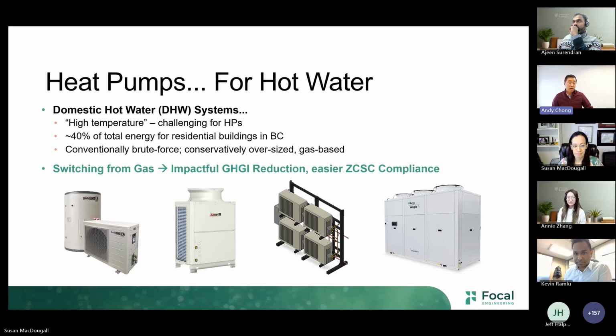Zero complaints, very robust system. And then coming to market, very credible international manufacturers are producing these commercial and institutional sized air source heat pumps, also based on CO2. Without going into a master class on CO2 heat pumps, these types of heat pumps are very good at one thing: generating domestic hot water. They work great at high lift. They are not good at doing radiant heating, not good at ventilation and heating, not good at really doing anything else. But they are so efficient and reliable at domestic hot water production, I really think this is going to be a huge trend for all buildings of all sizes over the next 5 to 10 years.